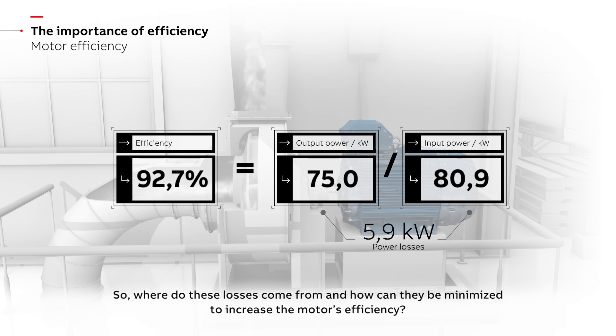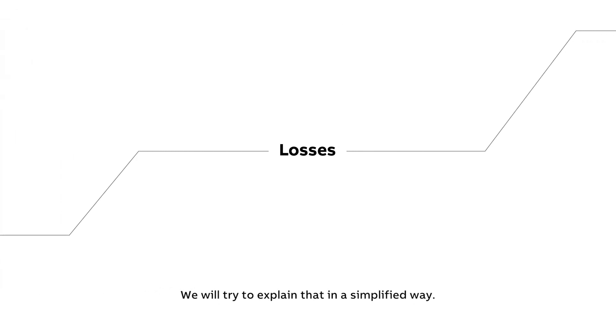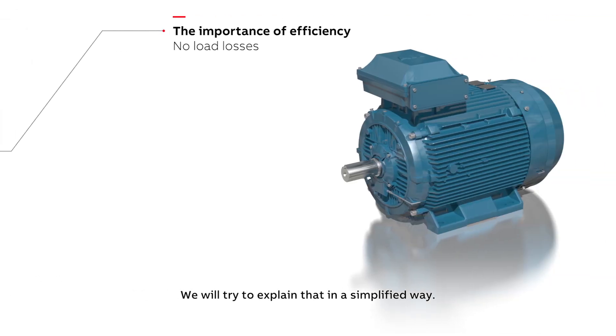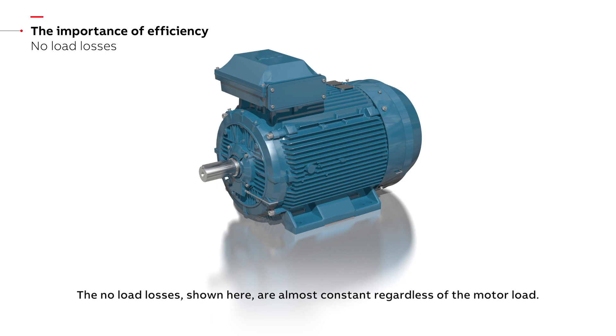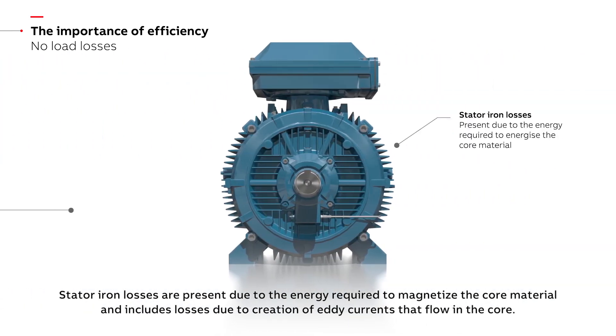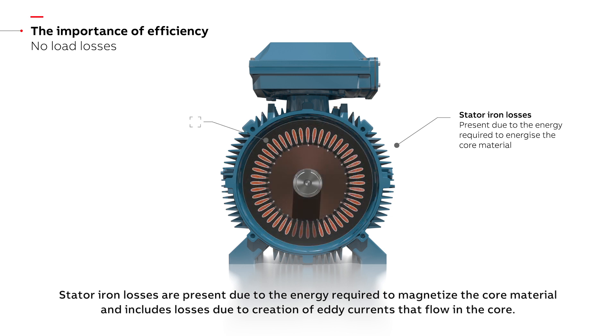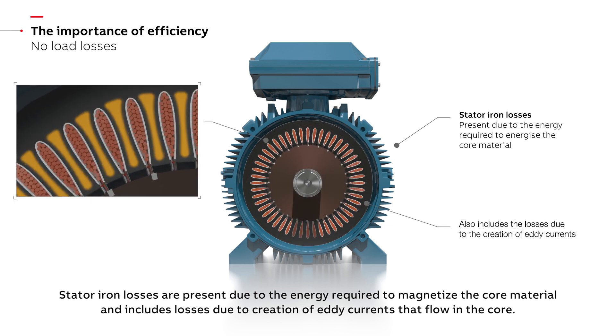So where do these losses come from and how can they be minimized to increase the motor's efficiency? The no-load losses shown here are almost constant regardless of the motor load. Stator iron losses are present due to the energy required to magnetize the core material, and include losses due to the creation of eddy currents that flow in the core.